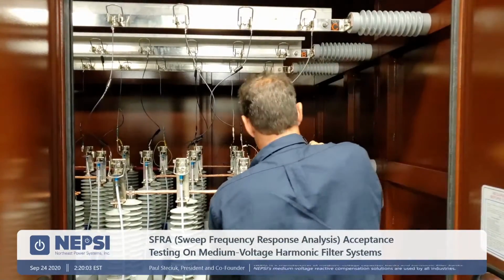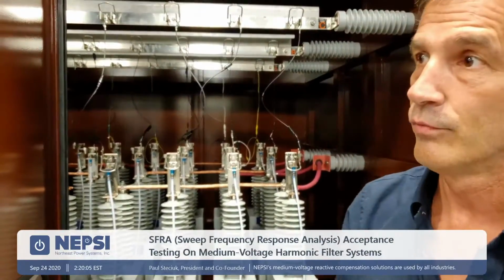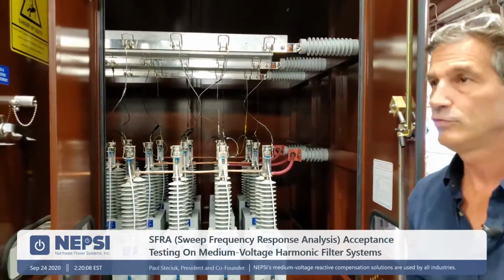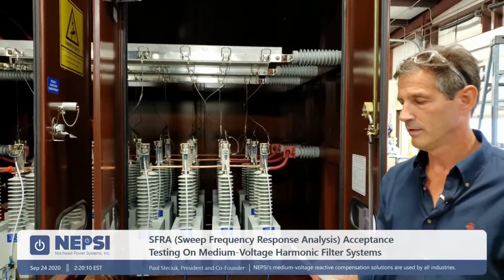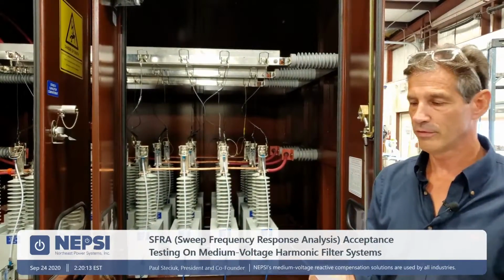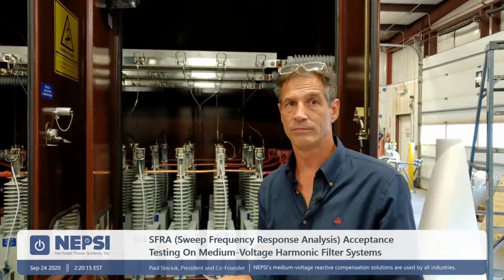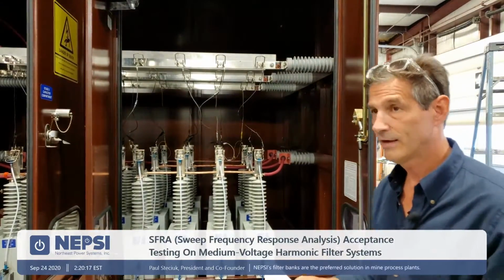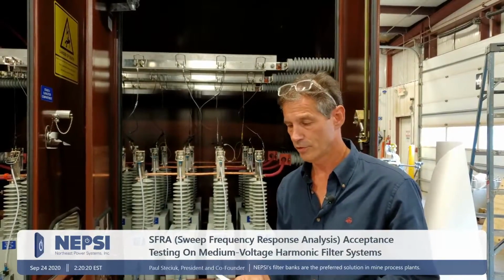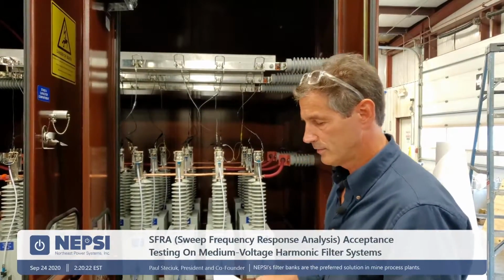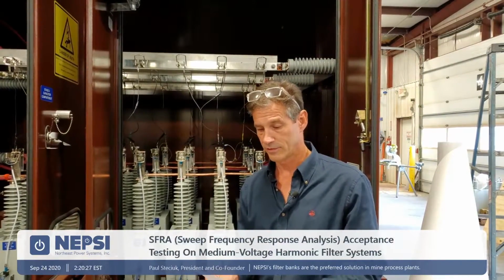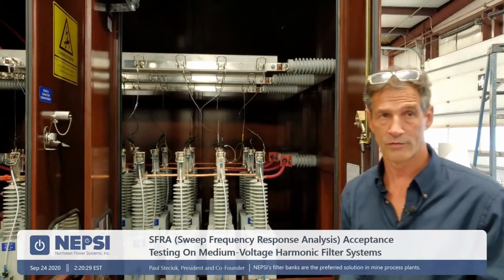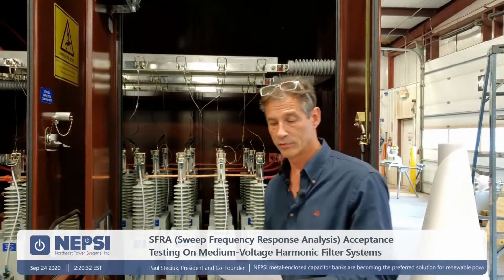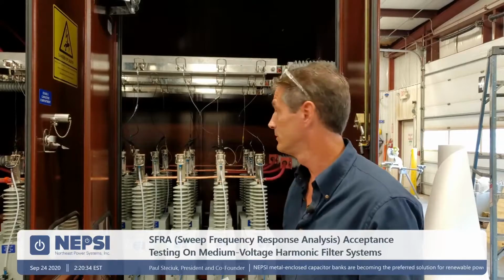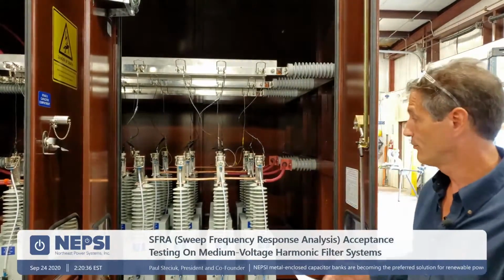And so what we're looking at here is this entire bank from one end to the other. It's a 25.2 megavar, 4.7 tuned filter rated at 34.5 kV and 50 hertz. It's built to an IEC standard. This equipment is being shipped to Europe, so it has to have that rating. Stage one is a 3.6 megavar bank with 6 capacitors. The second stage is a 7.2 megavar with 12 capacitors, and then the third stage is 14.4 megavars with 24 caps. You're looking at stage 3 right now.